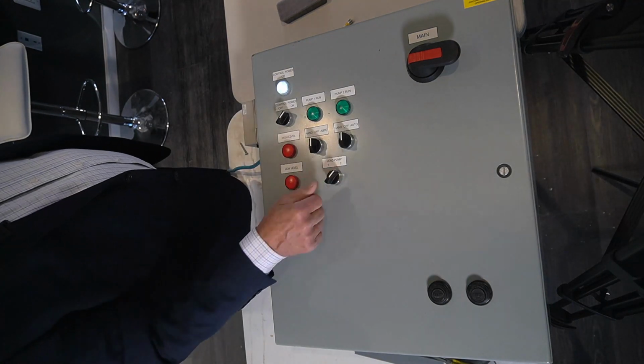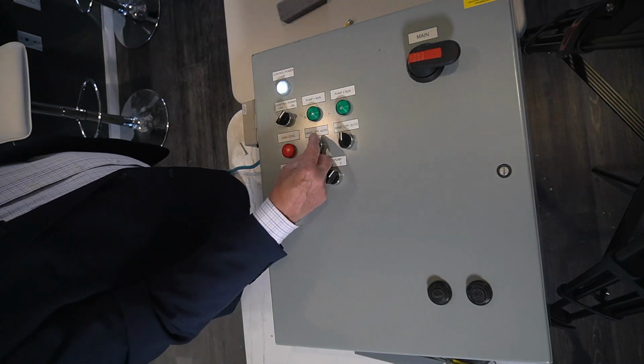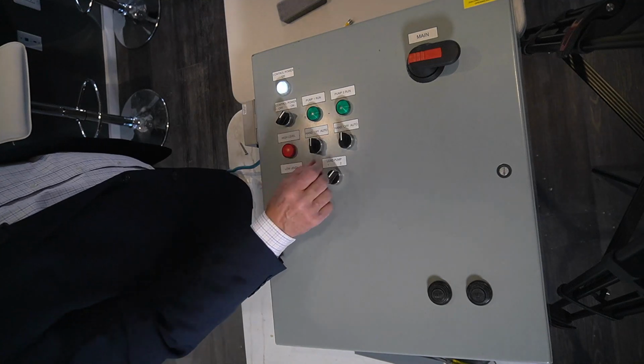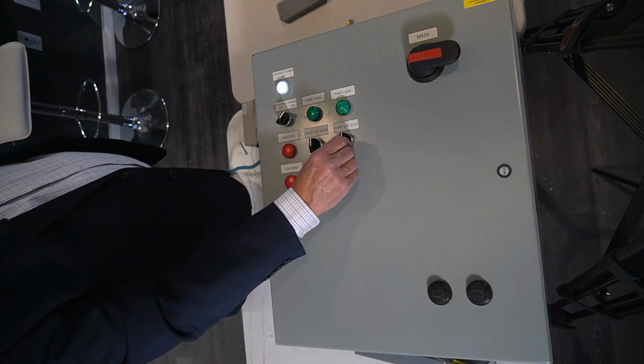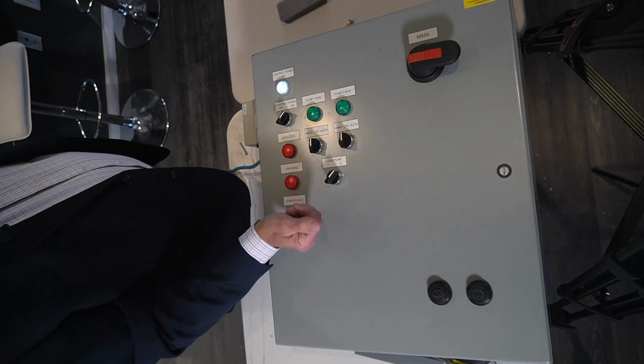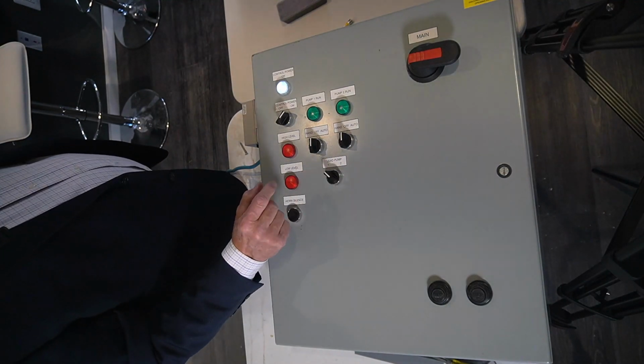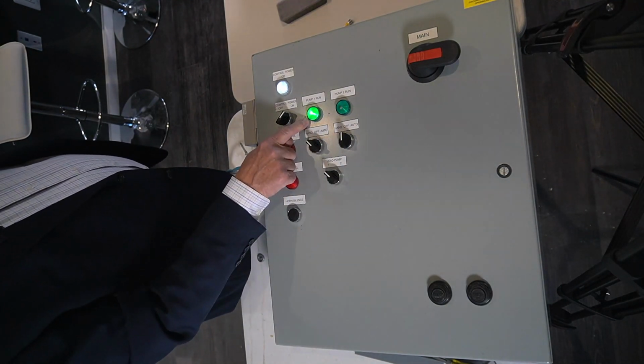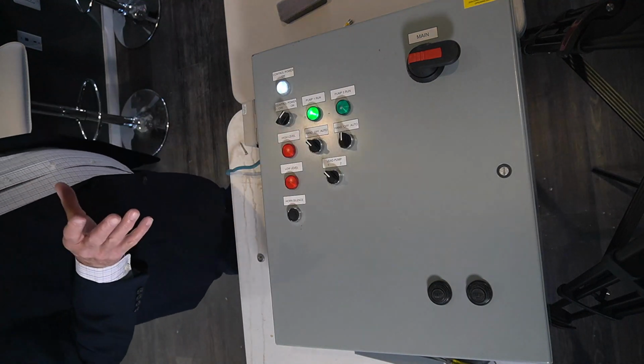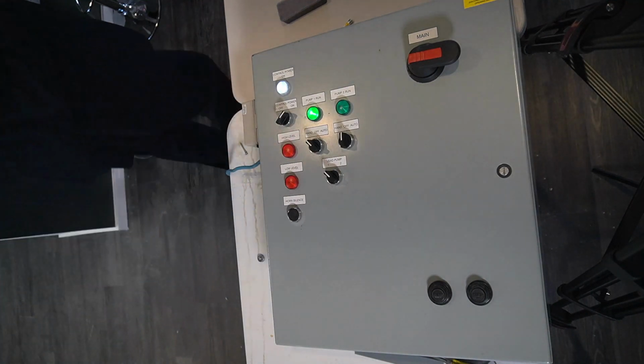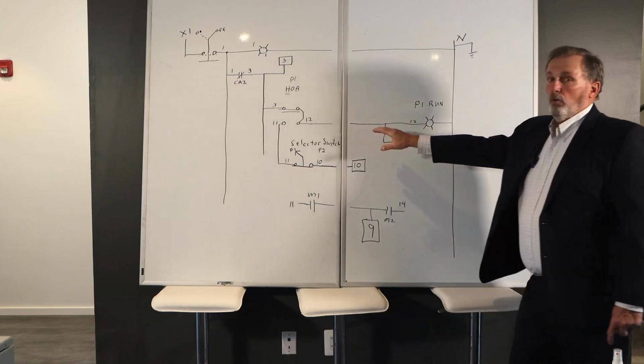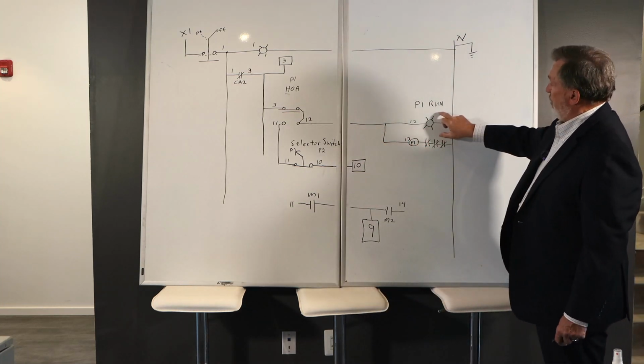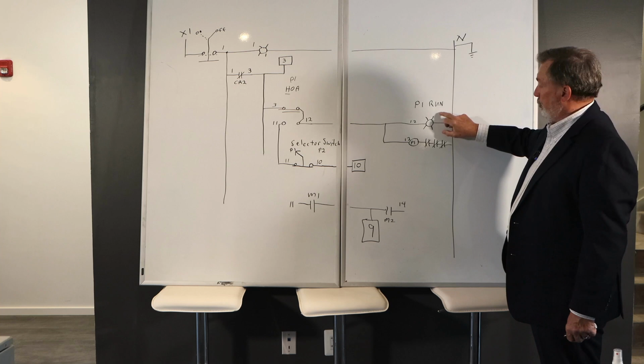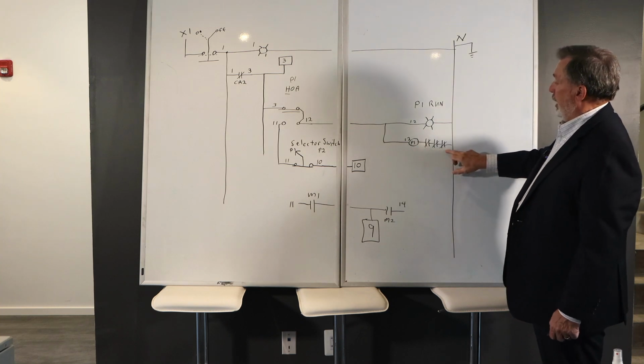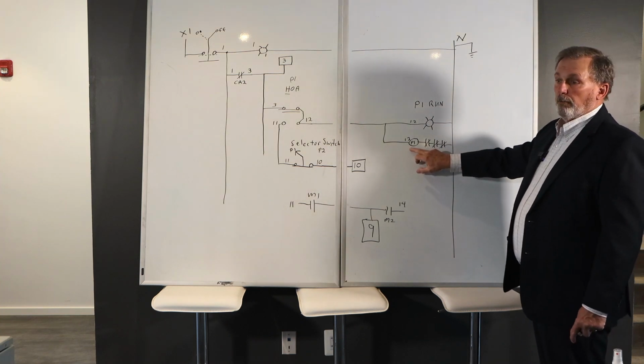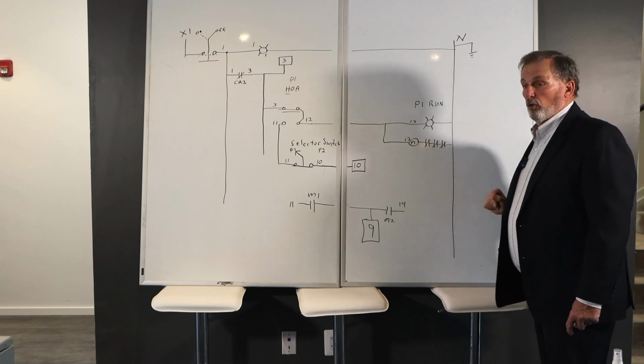Okay? If I go to lead pump 2, doesn't make any difference. When I'm in hand, I'm bypassing the selector switch. I can put either one in hand. Okay? This hand indication is a parallel output, so we have to put these two outputs in parallel. This is my pump run light. That's the green light we just had on. And this is the relay contact engaging. We're going to open up the cabinet and take a look at the relay pulling in.